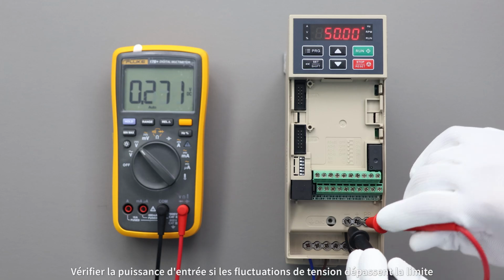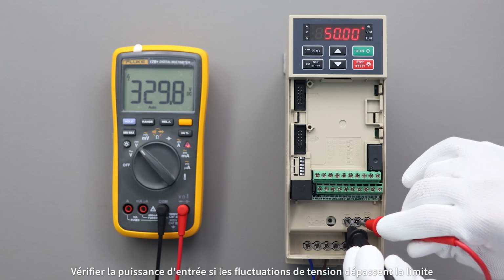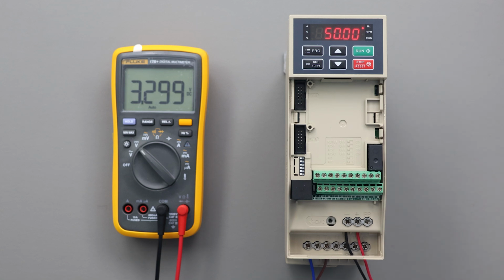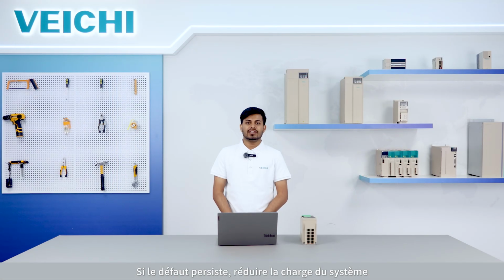Power voltage fluctuation. Check the input power if voltage fluctuation exceeds the limit. If fault still persists, reduce load on the system, or you can select a bigger capacity drive or connect a braking unit.